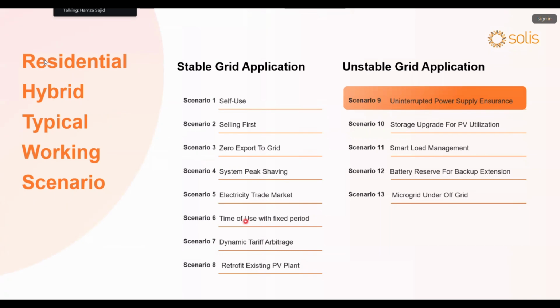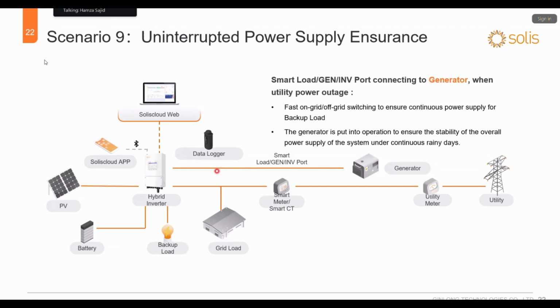Now, uninterrupted power supply assurance. Let's suppose there is a bank or some system with a very critical load. They have a generator, they have the utility available, and they want to use the system with no blackout. In this case they can install the generator on the gen port of the inverter, which is also called the smart port. You can attach the generator on this point.